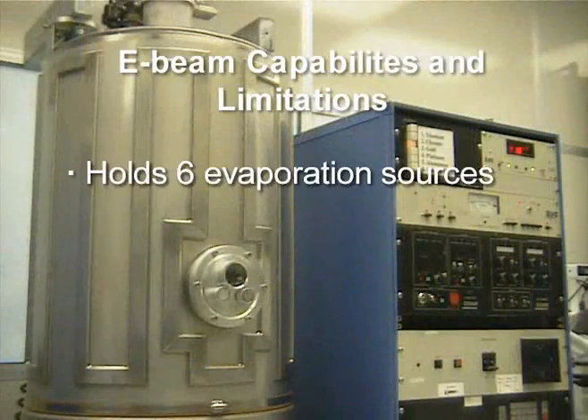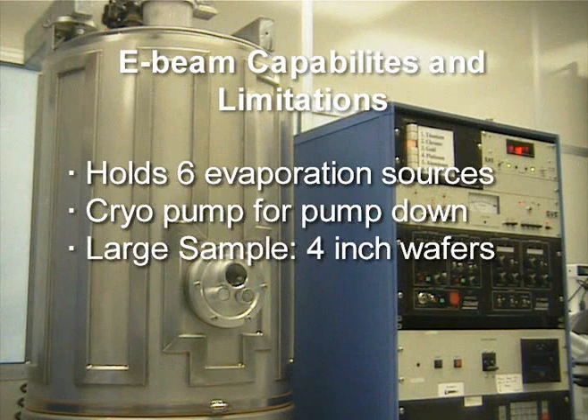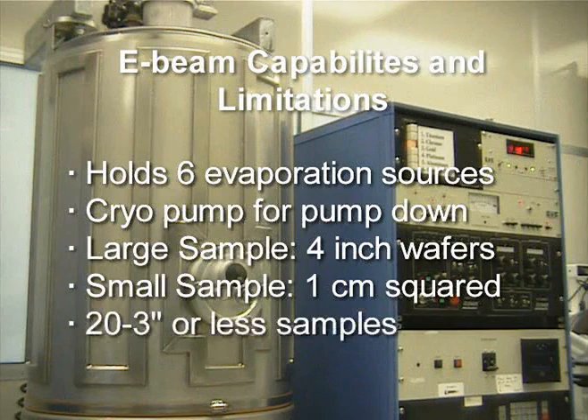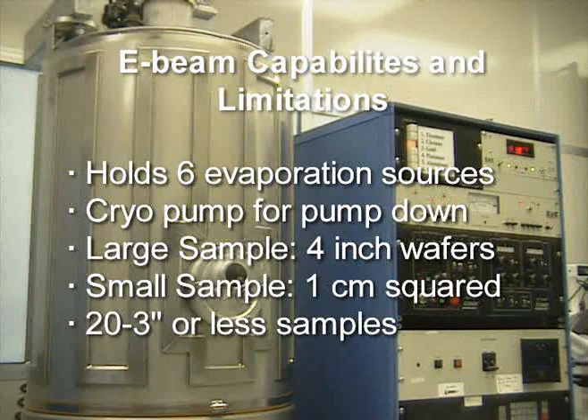The E-beam evaporator can hold up to six different evaporation sources. A cryopump is used for rapid pump-down. The E-beam can process samples in size from 4-inch wafers to less than 1-centimeter-squared samples using the process plate. It can also process 20 3-inch or less samples using the process dome. It is also to be noted that the backside heater is disabled.